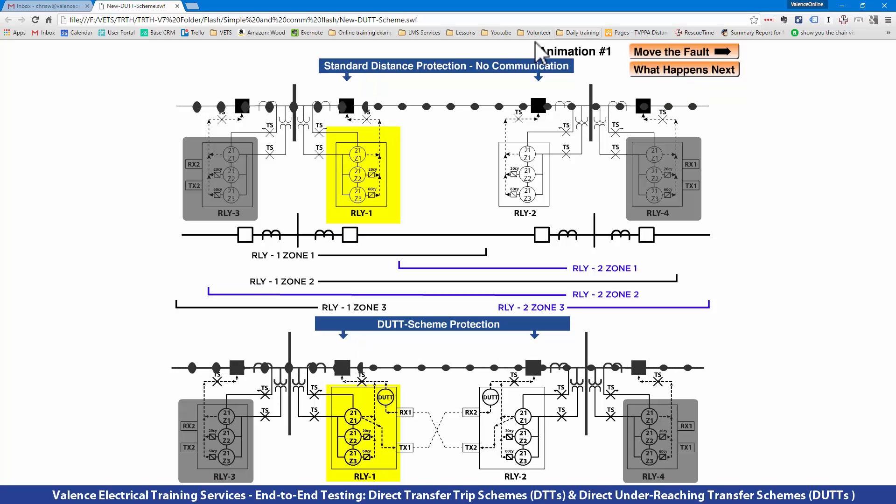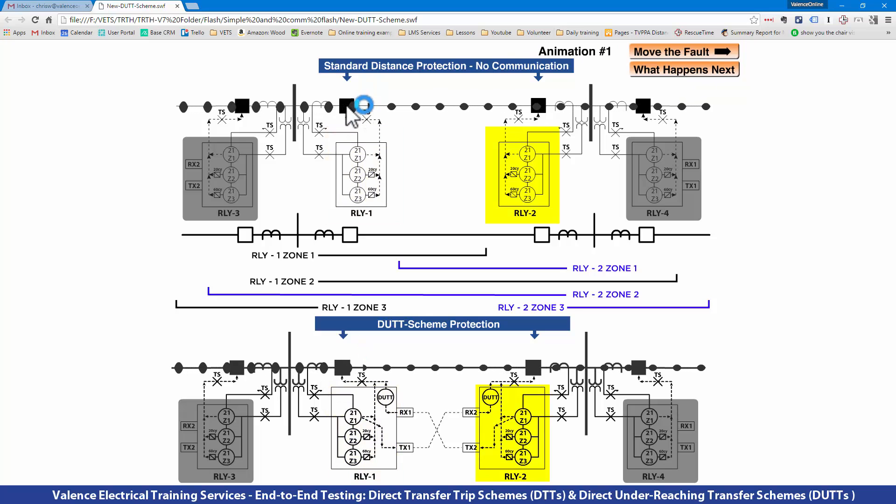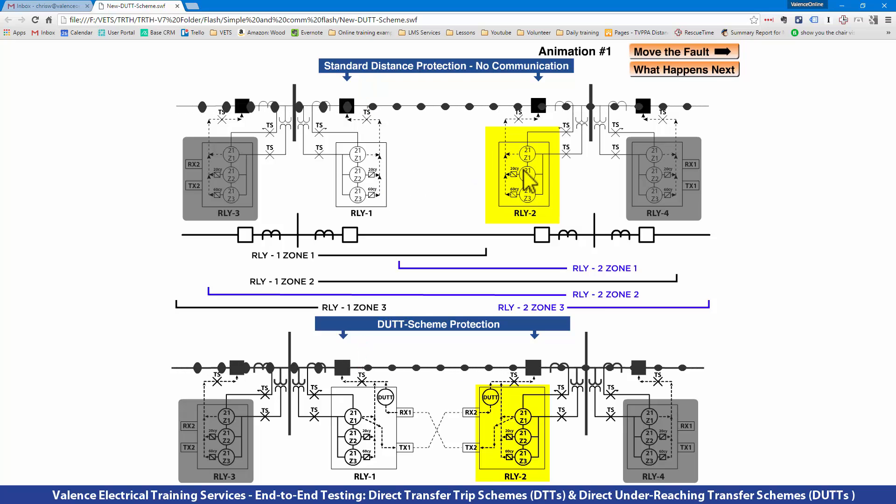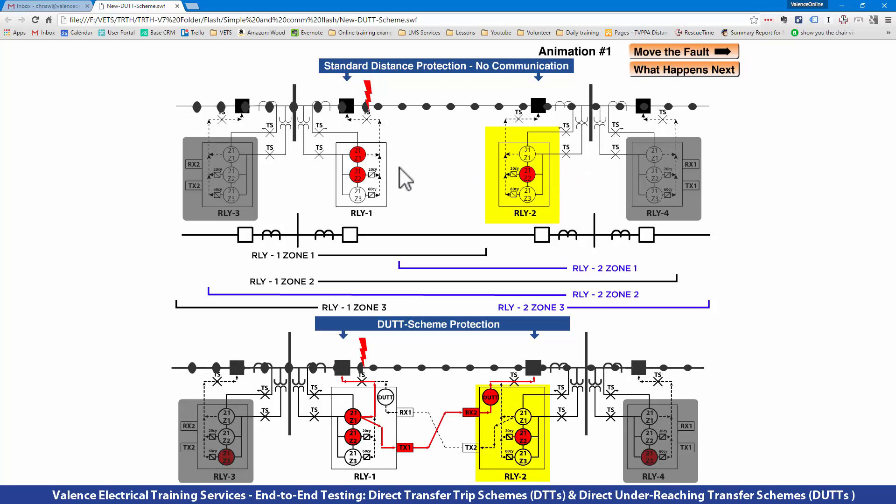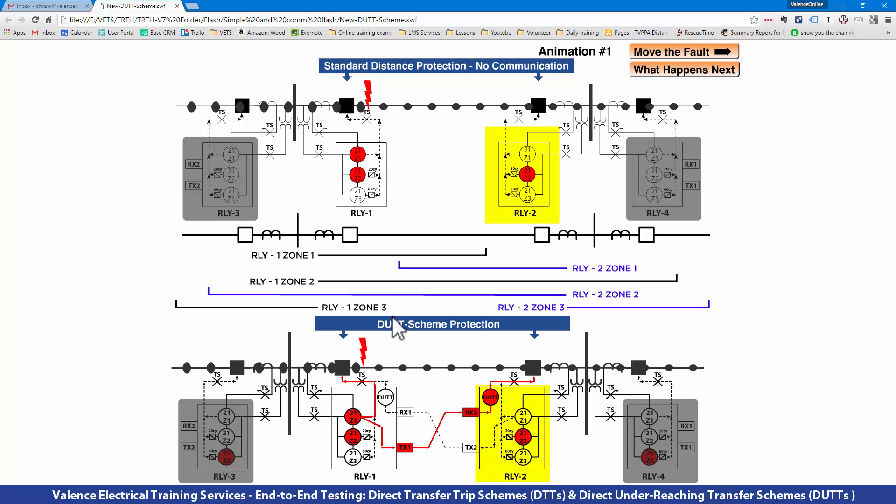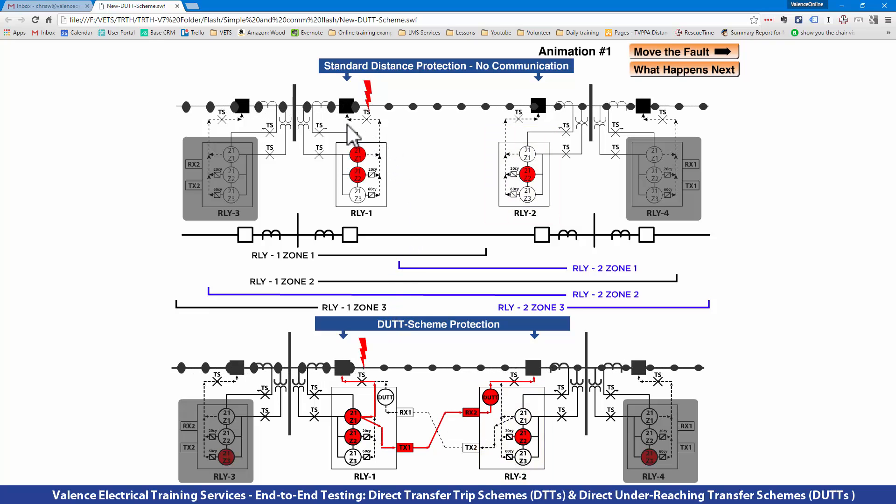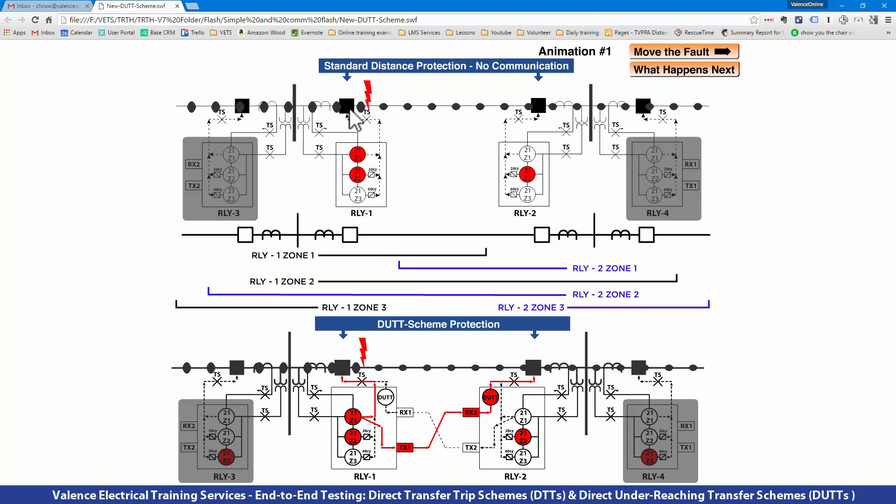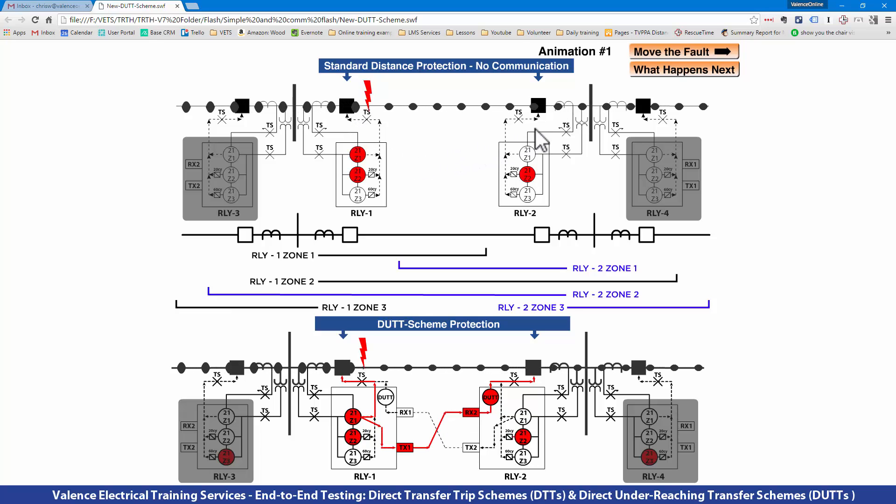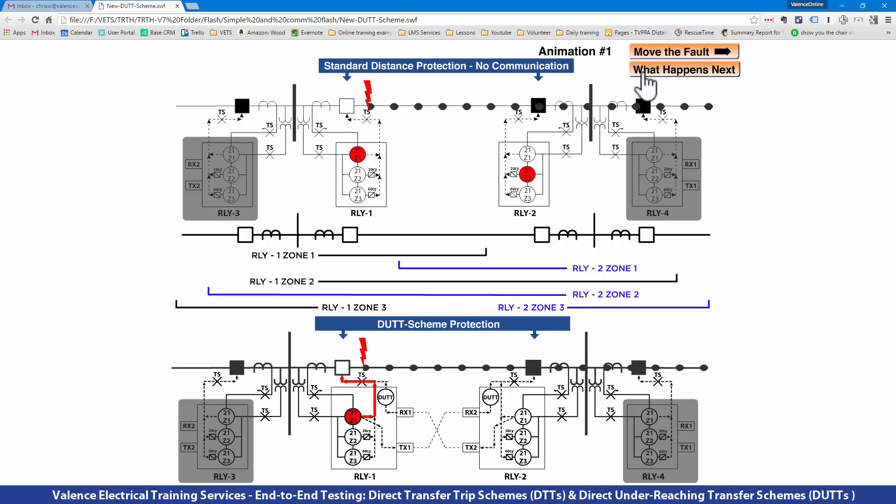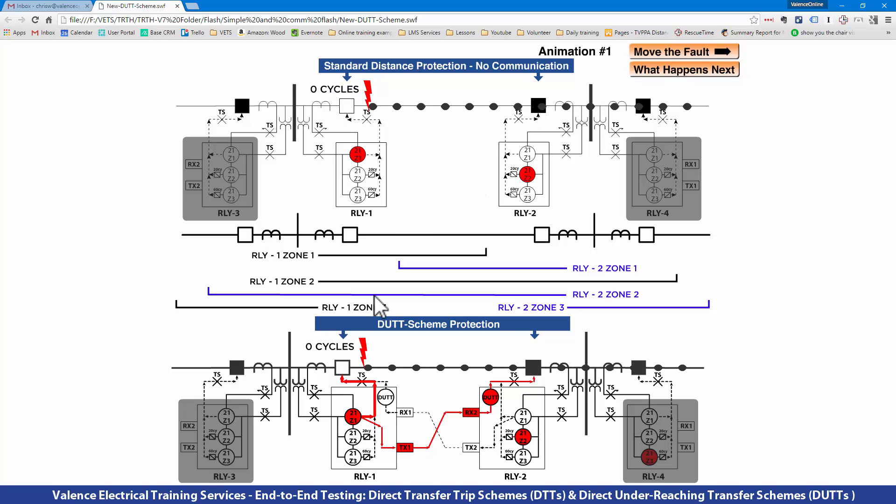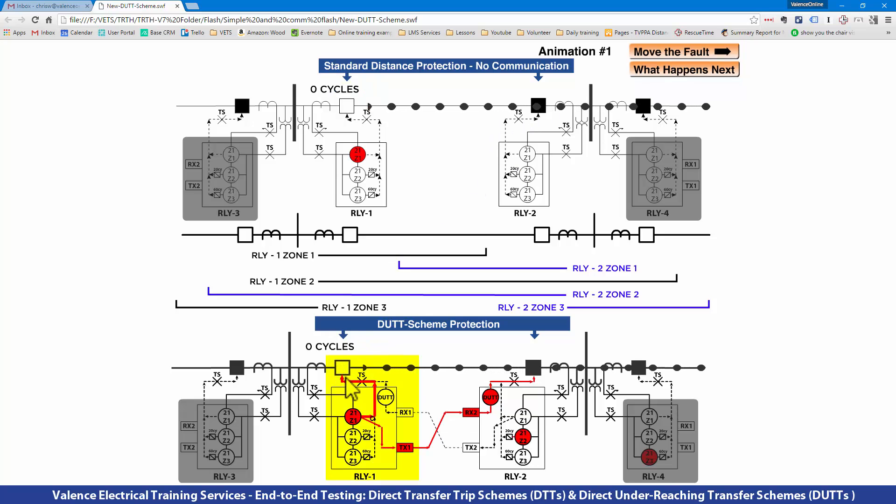Relay 2, because the fault is still on the line, is going to see Zone 2. The difference between the standard distance scheme and the DUTT scheme is that in the standard scheme, Relay 1 operates instantaneously and Relay 2 operates after a 20-cycle delay.